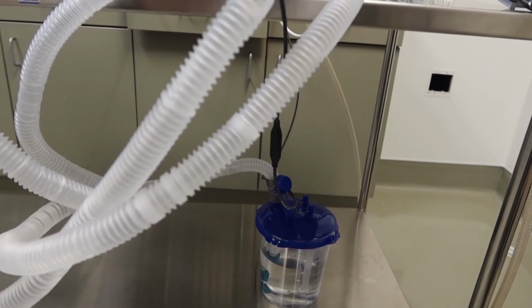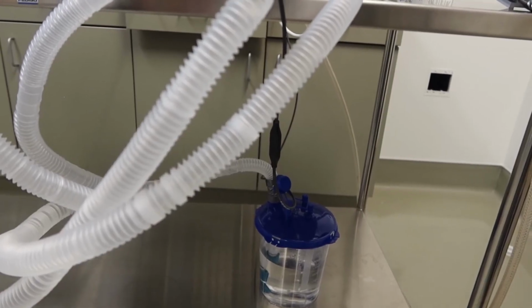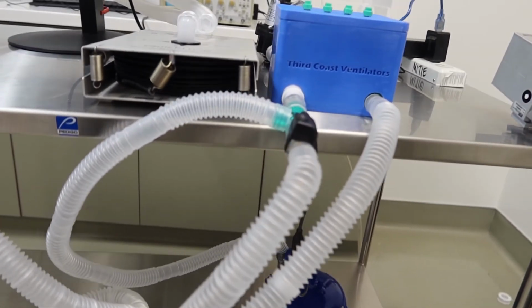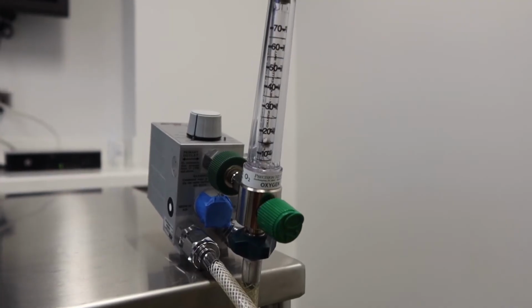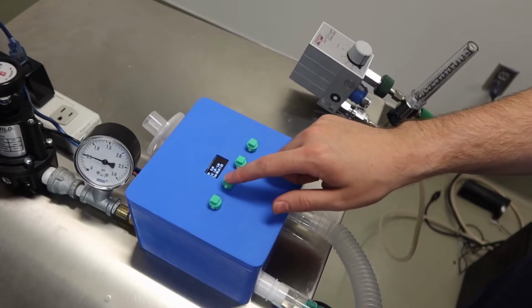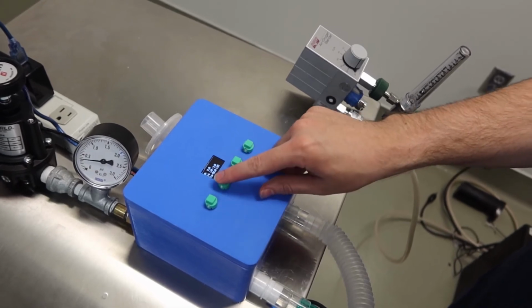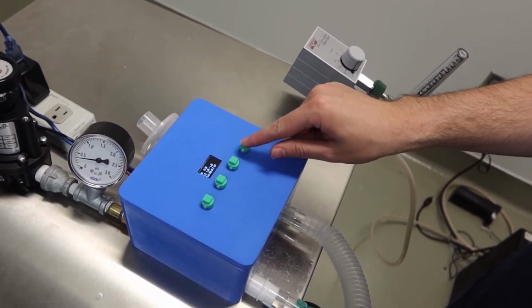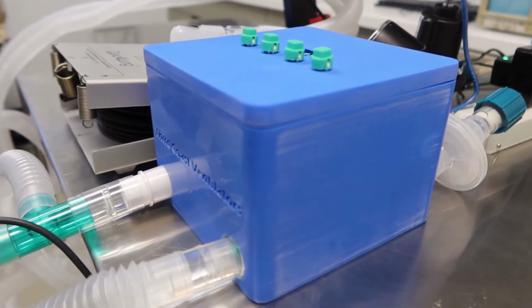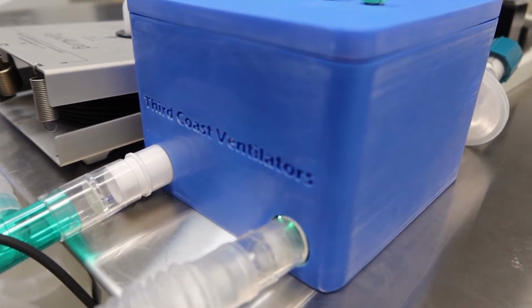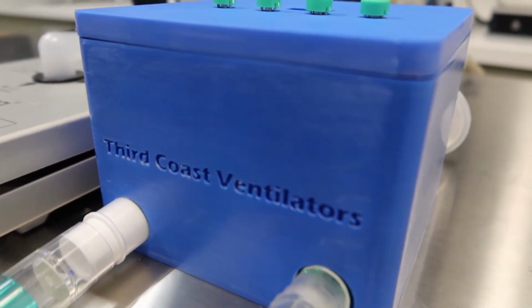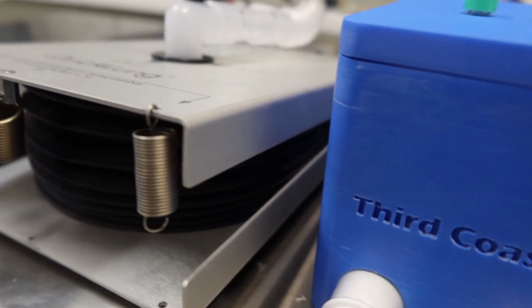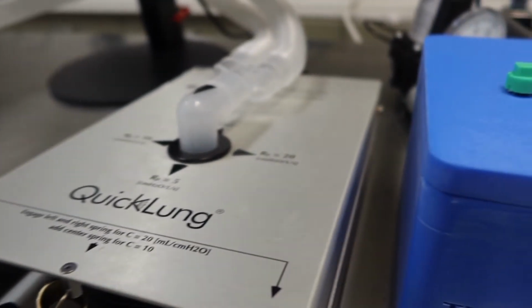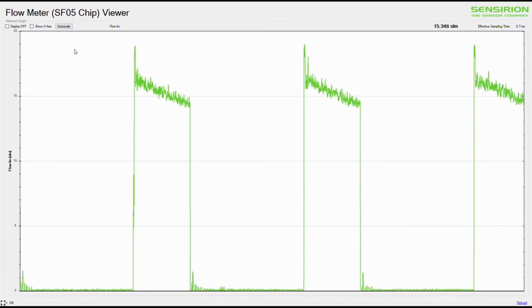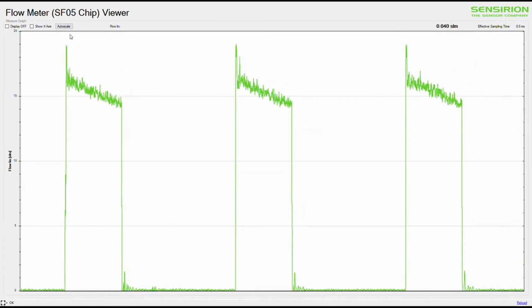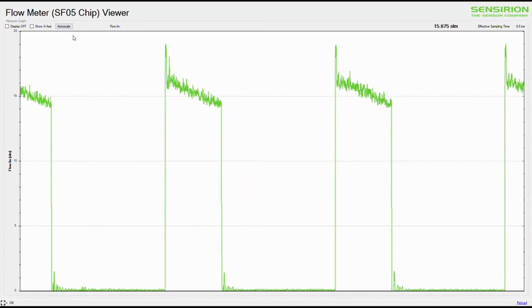With our addition of a simple water bucket, we can control peak inspiratory pressure. This allows us to not overpressurize the lung. We can fill the water bucket up to 30 centimeters of water. Downstream from the lung, we can control positive end-expiratory pressure. We can control these pressures between 1.5 and 20 centimeters of water, and this allows us to keep a baseline pressure within the lung so the lung does not collapse on expiration. Our design allows us to digitally control respiratory rate, which has been tested from 12 to 30 breaths per minute.